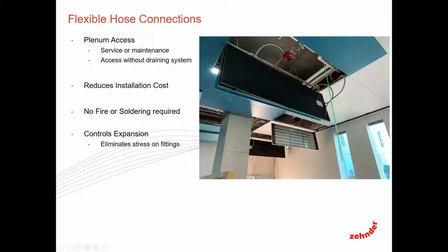You can see another panel down here with the activation. This hose hasn't actually been installed yet. So overall, it reduces your install costs, gives you some plenum access, and at the end of the day, it also helps with expansion and contraction, because those flexible hoses pick up that additional contraction, and it's not transmitted into the panel itself.